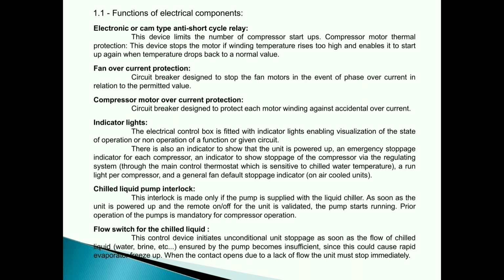Fan overcurrent protection. Circuit breaker designed to stop the fan motors in the event of phase overcurrent in relation to the permitted value. Compressor motor overcurrent protection. Circuit breaker designed to protect each motor winding against accidental overcurrent.